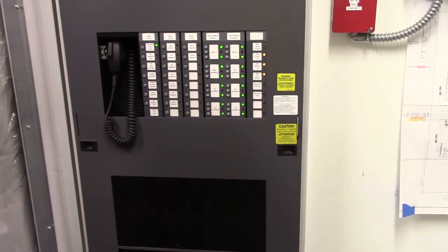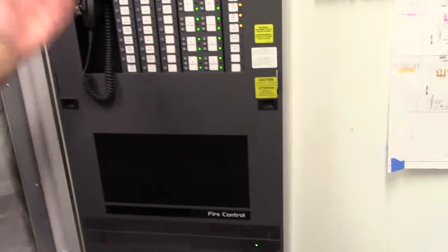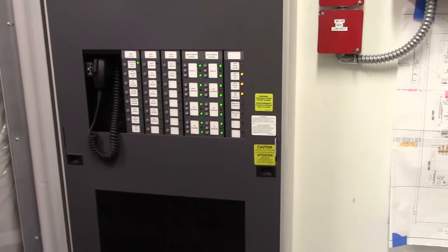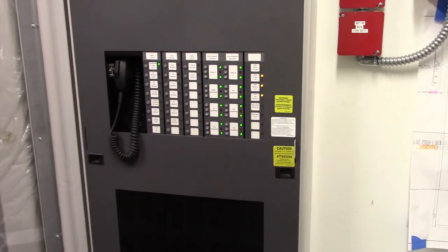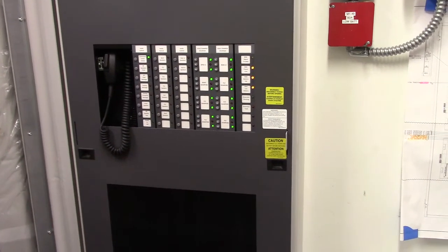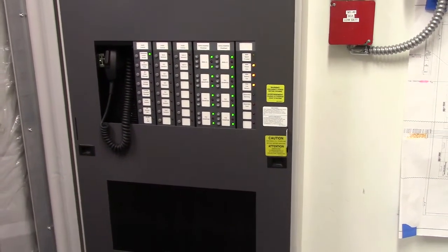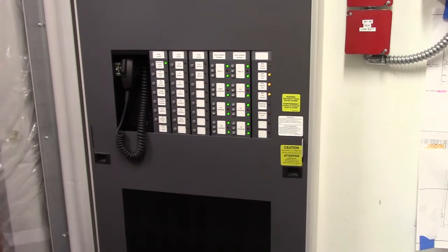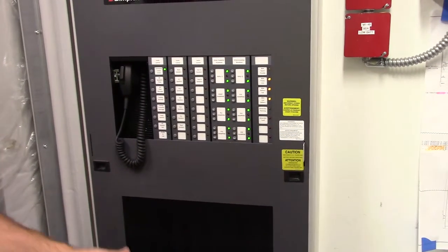The batteries should all be good for 4 years. You'll get the normal battery troubles if anything comes up. Actually, none of them are up right now, so I kind of half expected a low battery trouble, but going by the values I saw, these batteries are actually oversized for the building, quite a bit. So you shouldn't have battery problems.